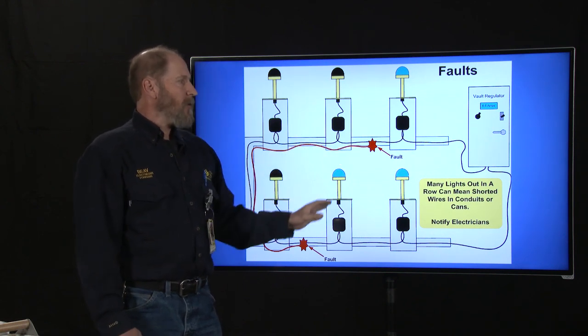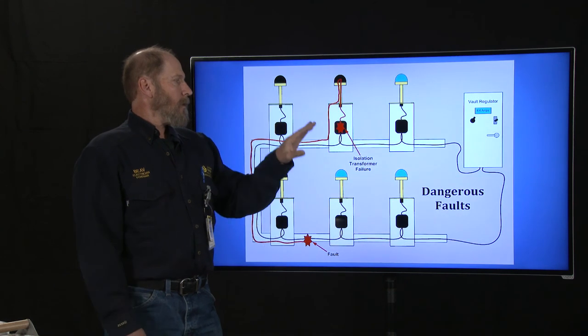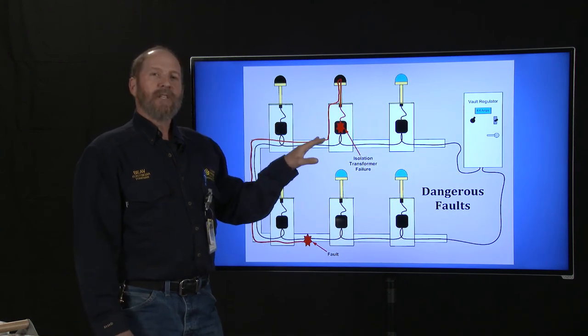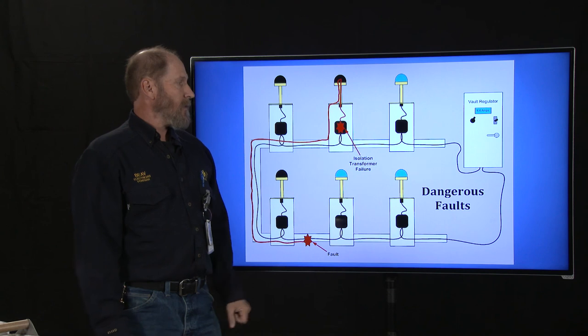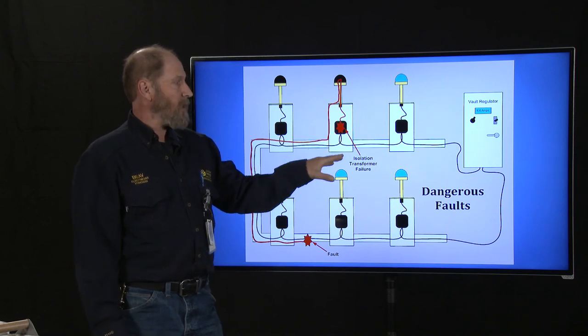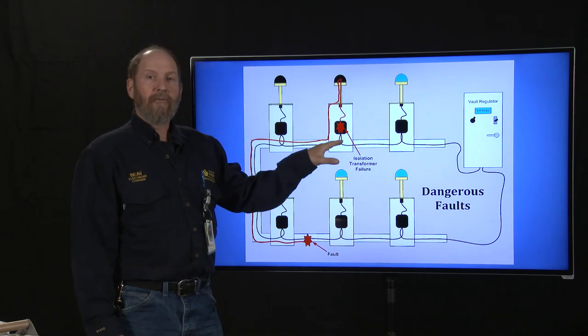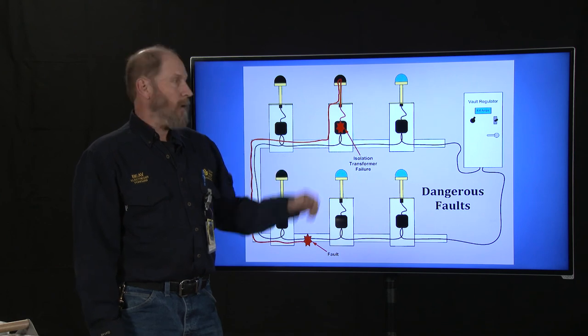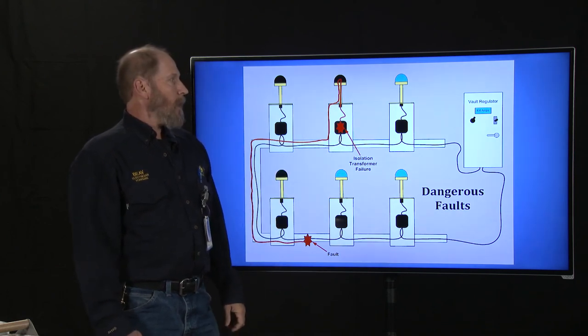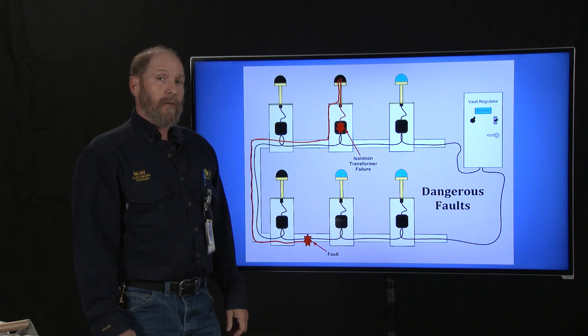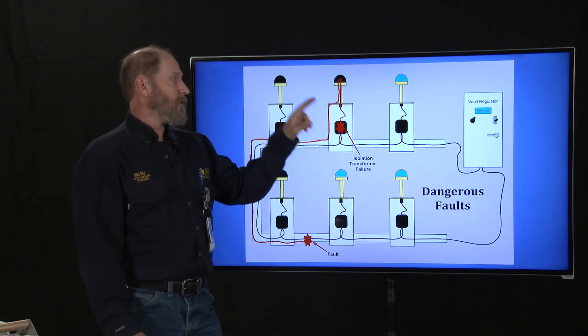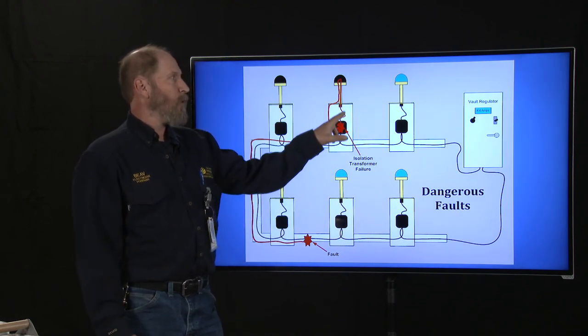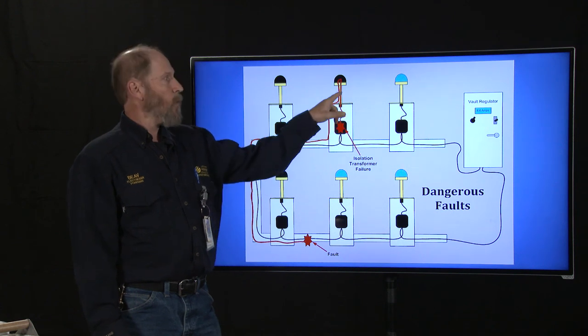Everything is going on down under the ground. But there are situations where faults become very dangerous, and this is the situation. An isolation transformer can fail, and we know they do fail, and far more often than we ever thought.